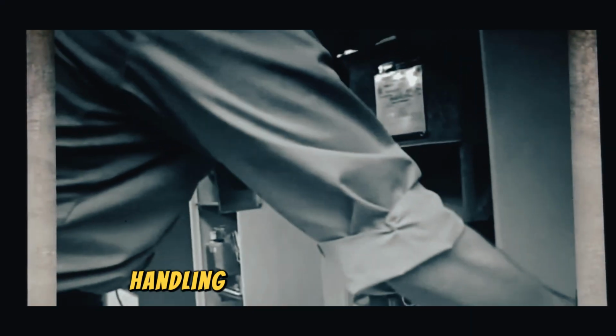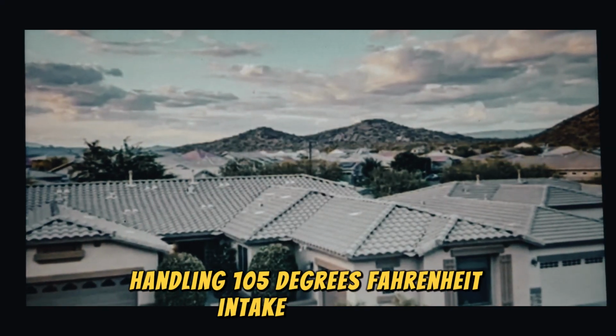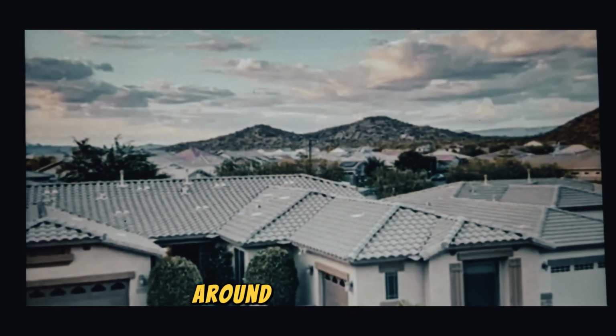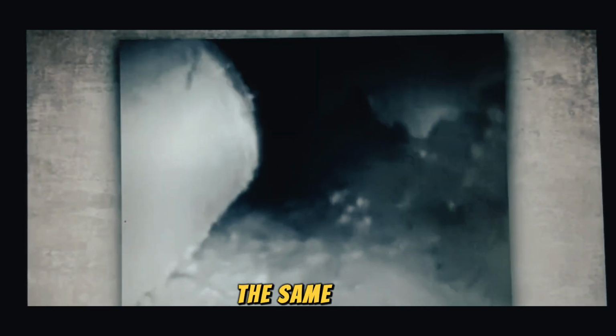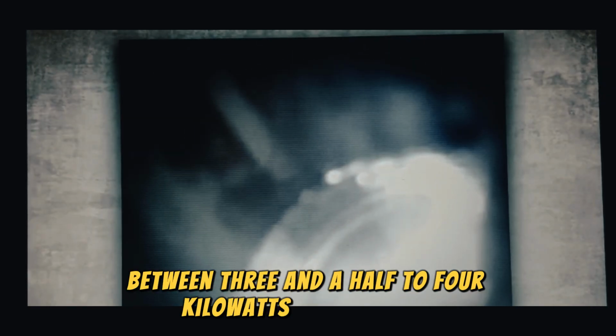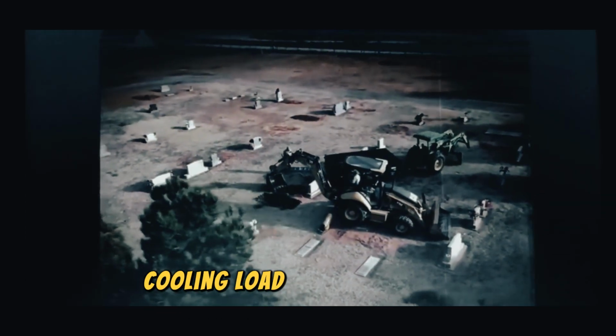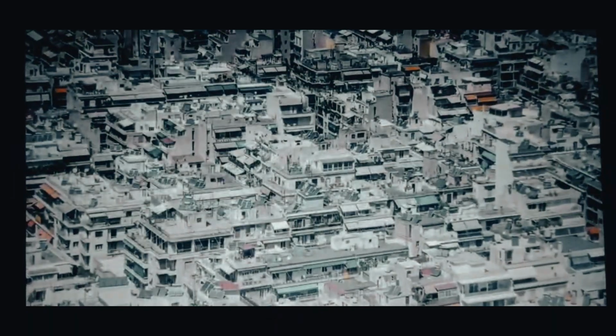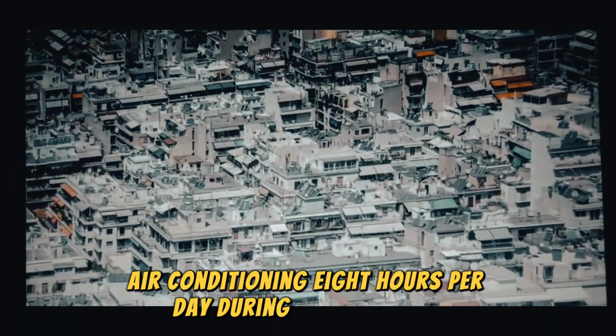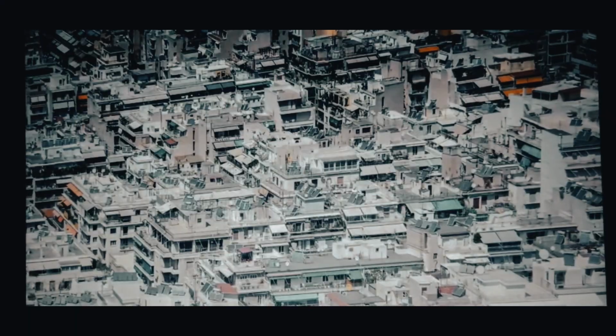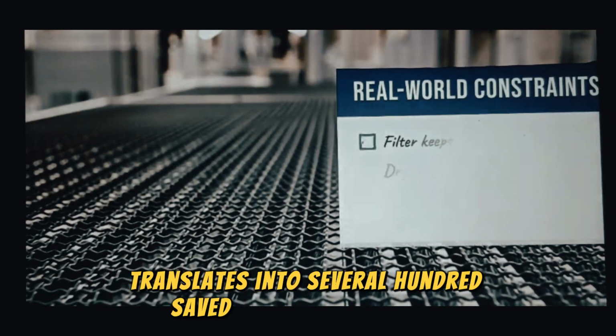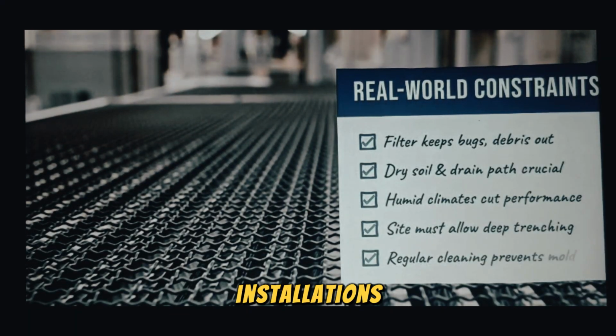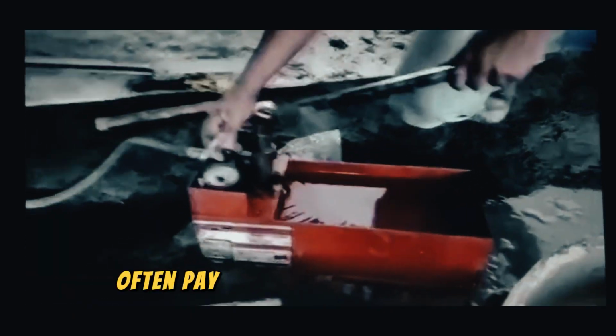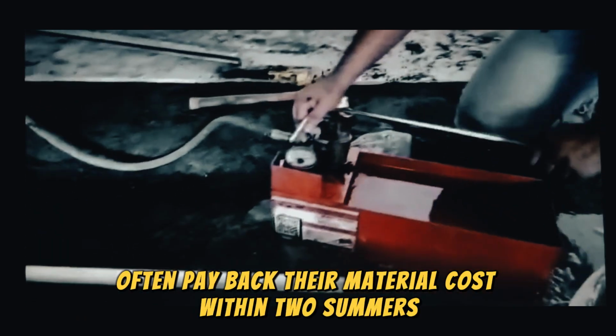A compressor handling 105 degrees Fahrenheit intake air draws around 6 kilowatts. The same unit handling 68 degrees Fahrenheit pre-cooled air draws somewhere between 3.5 to 4 kilowatts for the same cooling load. For a household running air conditioning 8 hours per day during a hot summer, that reduction translates into several hundred dollars saved per cooling season. Installations often pay back their material cost within 2 summers.